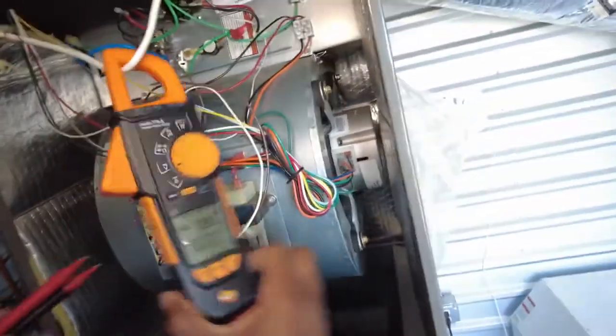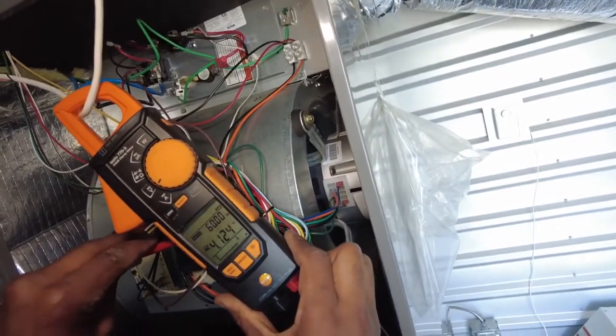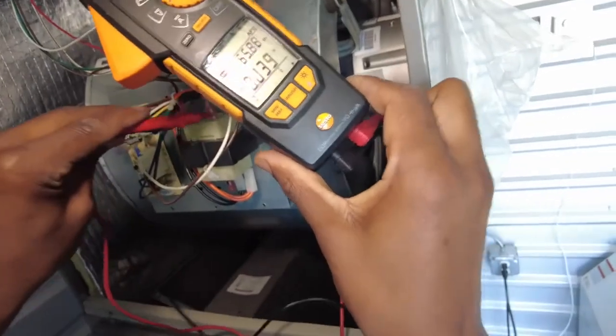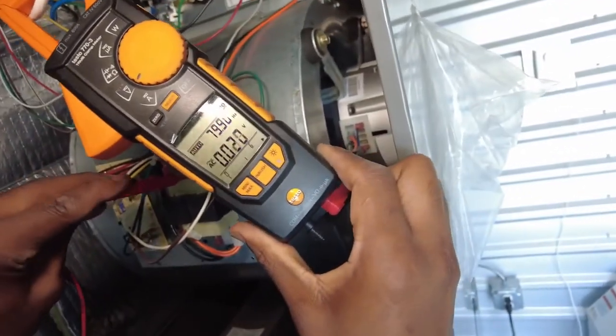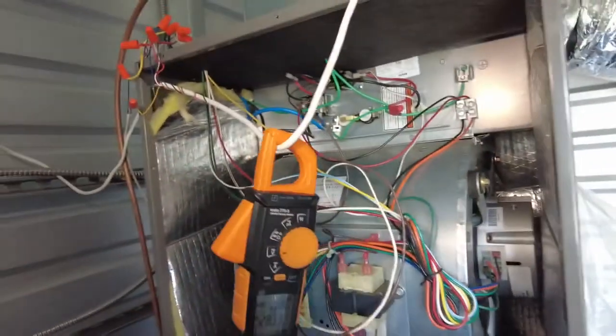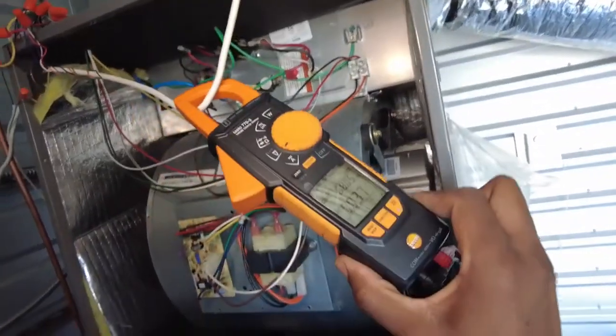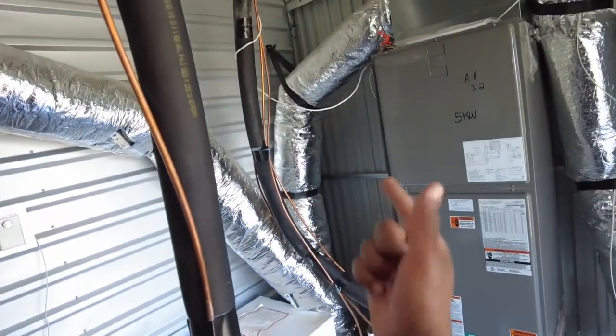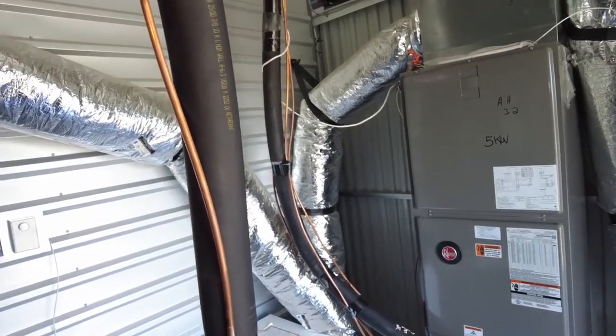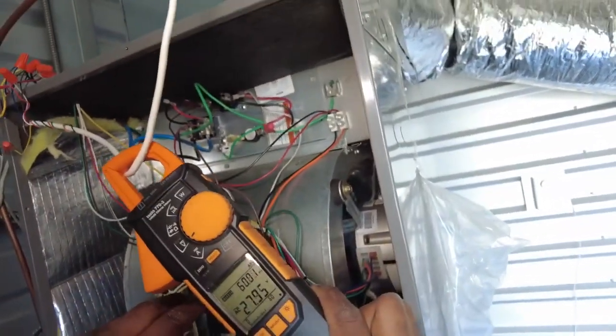Give it back its power. There you go, 28 volts. Now we should have enough boost to pull that contactor in and keep it in. And like I said, I just checked that unit. That one's got 22 volts too going to the contactor. It's holding, but it needs to be swapped as well. So all the units probably in this whole facility are going to have to be changed over. At 28 volts looks a whole lot more reasonable.